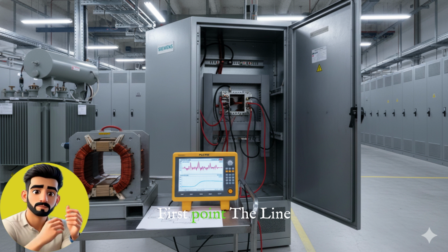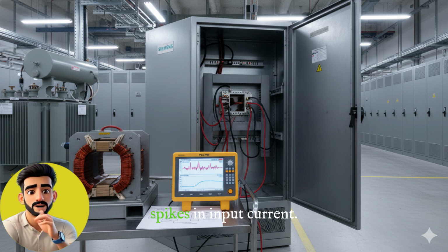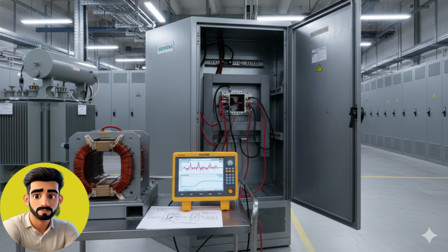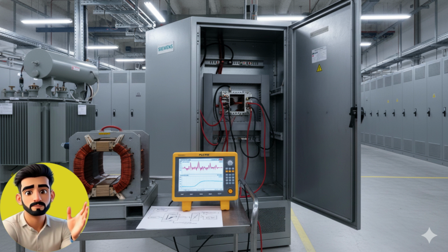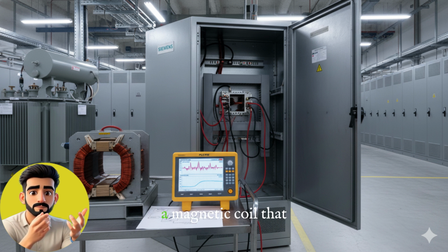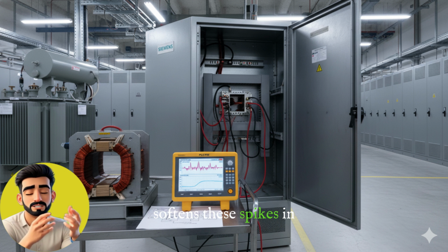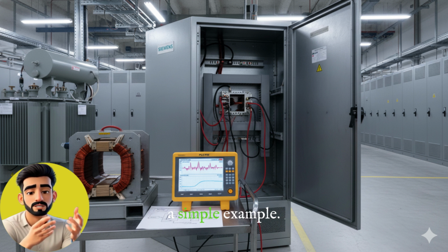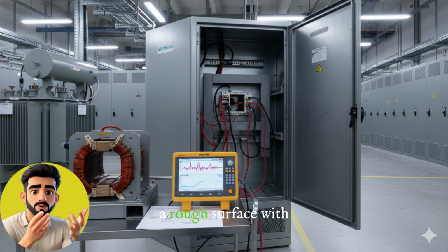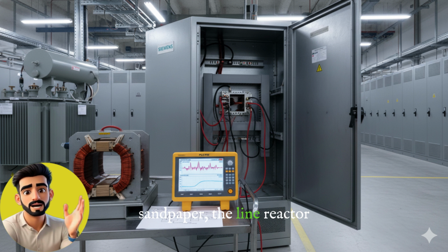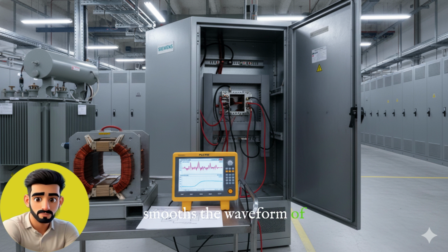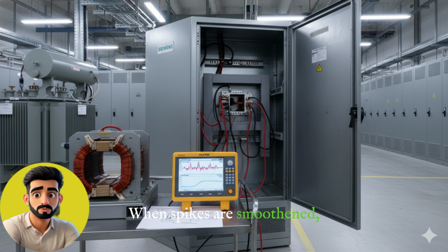First point. The line reactor rounds off the spikes in input current. The rectifier of the VSD draws current in small spikes. These spikes create harmonics in the system. The line reactor is a magnetic coil that softens these spikes in current. Think of it with a simple example. Just as we smooth a rough surface with sandpaper, the line reactor smooths the waveform of the current. When spikes are smoothened, harmonics naturally decrease.